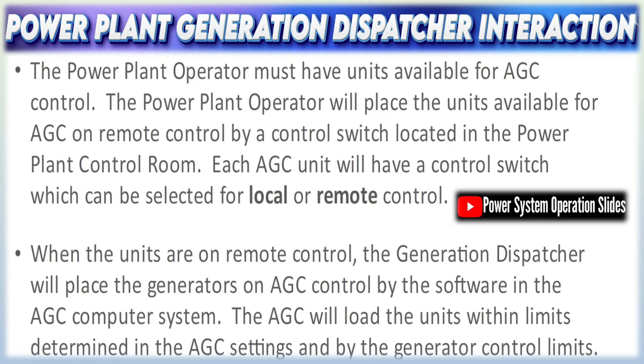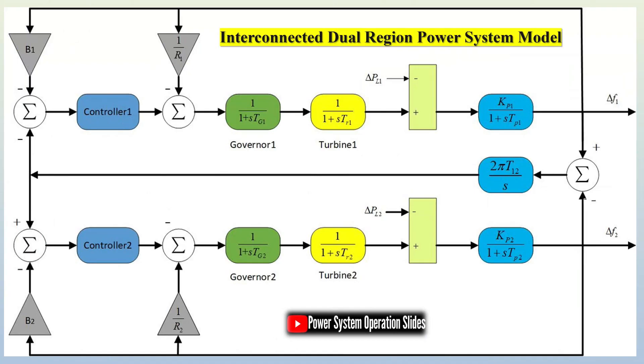In response, AGC instructs generators to reduce output. Negative A.C.E. suggests under-generation or importing more power than planned and a likely frequency drop, so AGC then calls for an increase in generation. By continuously making adjustments to drive A.C.E. towards zero, the system effectively balances the load-generation difference and stabilizes the overall grid.